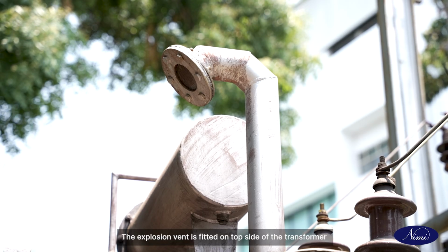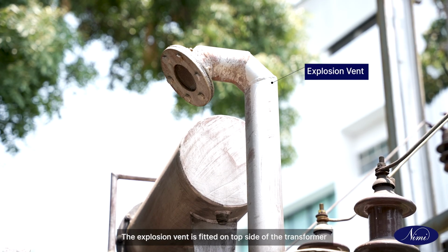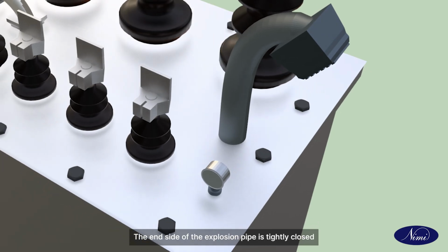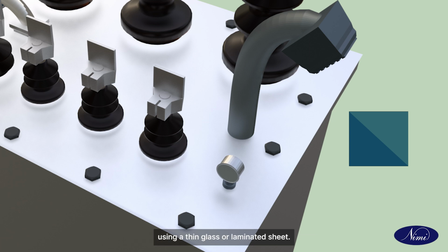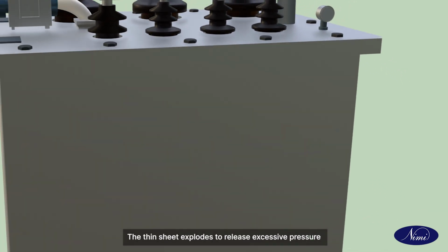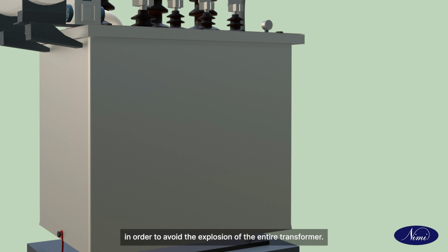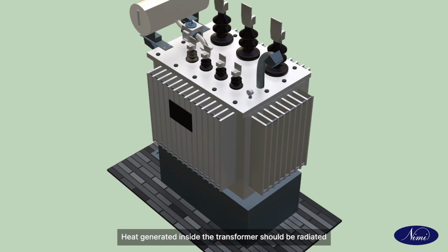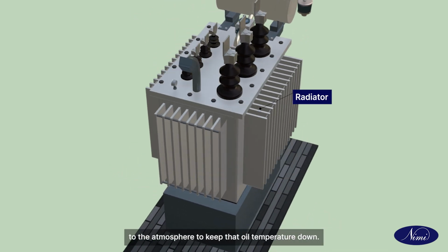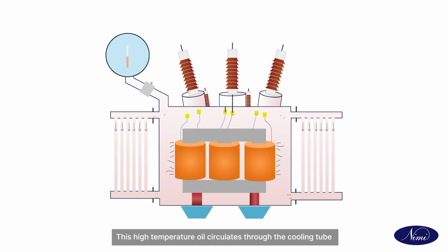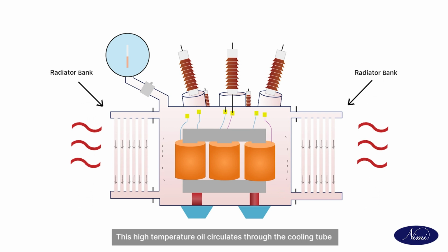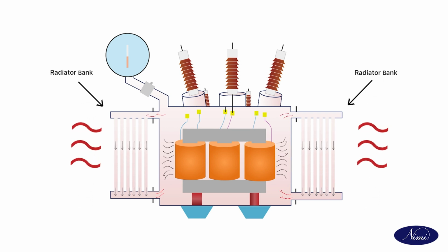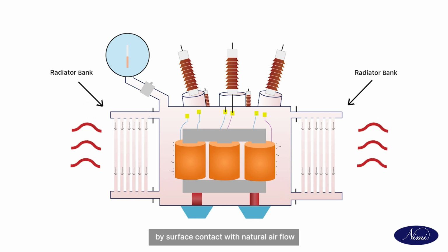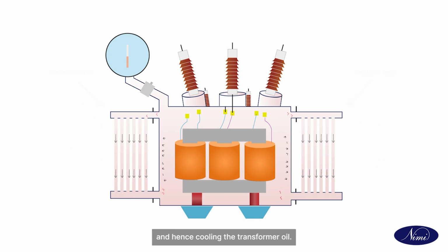The explosion vent is fitted on the top side of the transformer as a pressure release device. The end side of the explosion pipe is tightly closed using a thin glass or laminated sheet. The thin sheet explodes to release excessive pressure built up in the transformer in order to avoid explosion of the entire transformer. Heat generated inside the transformer should be radiated to the atmosphere to keep the oil temperature down. This high temperature oil circulates through the cooling tube and dissipates heat to the atmosphere by surface contact with natural airflow, and hence cools the transformer oil.